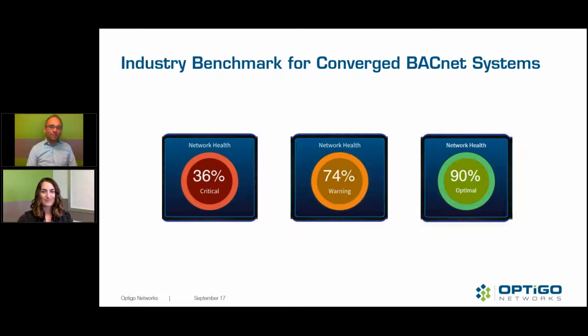Yes. So as many of you know, our goal with Visual BACnet right now is to become the industry benchmark for converged BACnet systems. BACnet devices are obviously tested by BTL, and they're certified, and they're guaranteed to work as a BACnet device certified to the standard. But when you're building out a building, you're using devices that have never in the world necessarily been in the same configuration, talked to each other before. And ideally the standard covers you, but there's a lot of room for error.